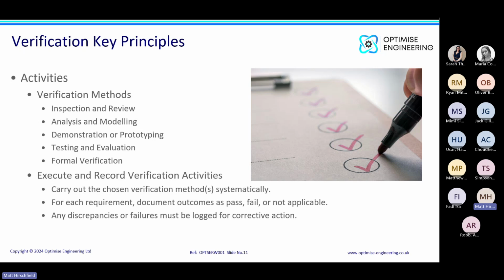Execution and recording of the verification activities. We're carrying out our chosen verification methods systematically. We go through, we check, we make sure everything's being verified. For each requirement that we document, for each verification step that we take, we document the outcomes as pass, fail, or not applicable. Any discrepancies or failures must be logged for corrective action. So anything that doesn't pass verification needs to be reported, analysed, and understood why. And then we need to determine what the correct course of action is to resolve that issue.